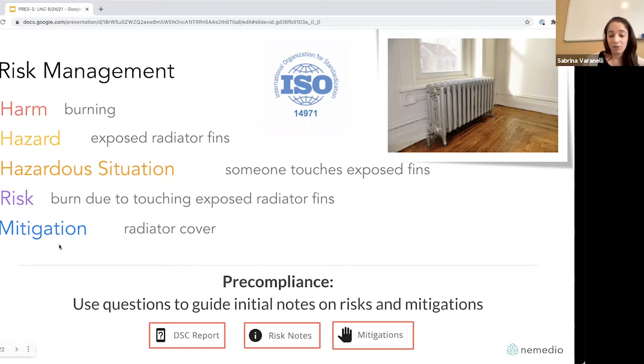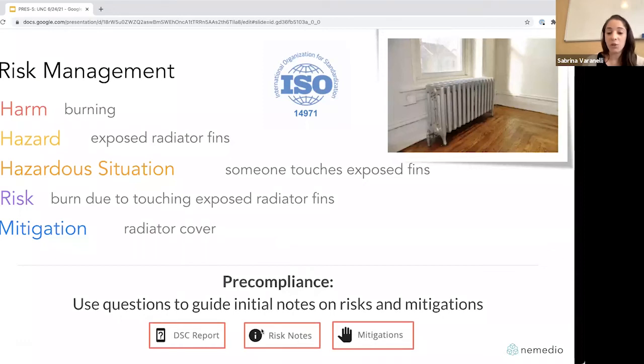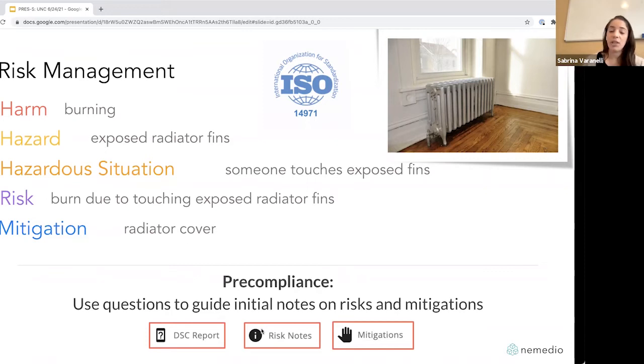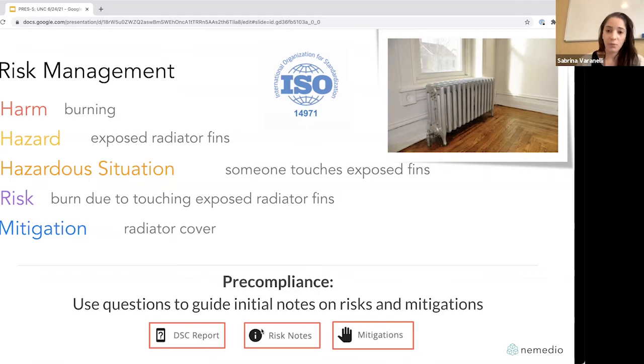It's very easy for engineering teams to write all the risks associated with their device. It's a little harder to do the full back analysis to figure out severity and probability to comply with ISO 14971. At your earliest stage, what we ask companies to do is write the risks down — we call this a risk note. This risk note will turn into a full-blown system hazard risk analysis later on. Even just keeping a running tally of the risks your product has while you think of them is one of the easiest ways you can help yourself later.